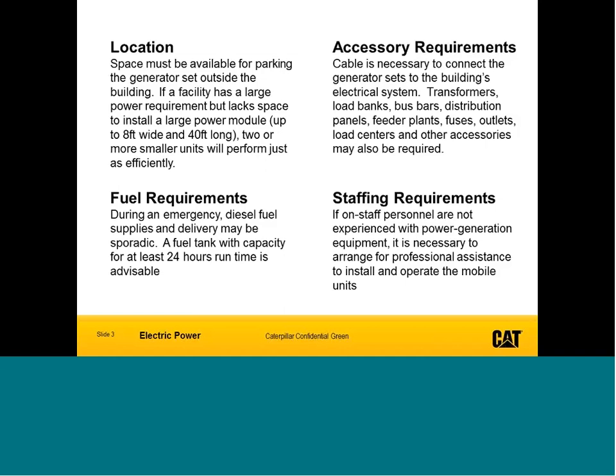Next we want to talk about your fuel requirements. Most emergency standby generators, at least the mobile ones you'd get for a temporary period, come standard with a 24-hour fuel tank. That's typically measured at 24 hours of running at 75% of their capacity load. So depending on how much power you're actually drawing off that piece of equipment, there's an ongoing logistical consideration to refuel that genset.